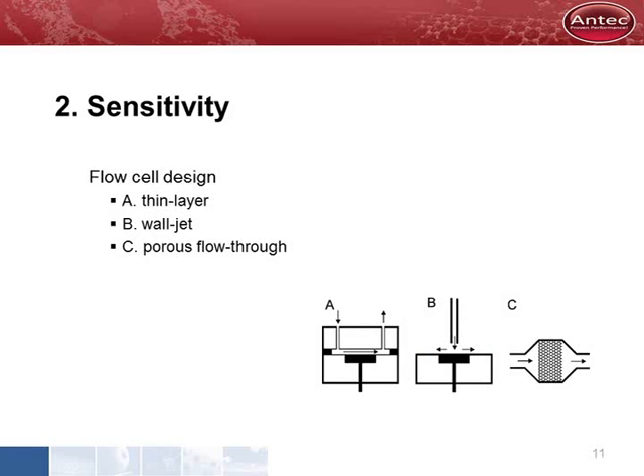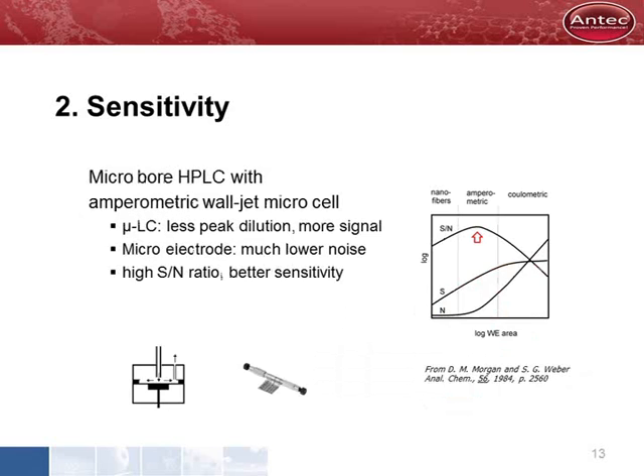Our second requirement is to develop a method with sufficient sensitivity. We put quite some effort into cell design to meet the required sensitivity. Antec developed a wall-jet cell which has a huge advantage: the cell can be miniaturized and used in micro-LC without losing performance. It is well known that micro-bore LC has less peak dilution, resulting in more signal. Miniaturization using micro-electrodes results in low noise, so the combination results in an improved signal-to-noise ratio.